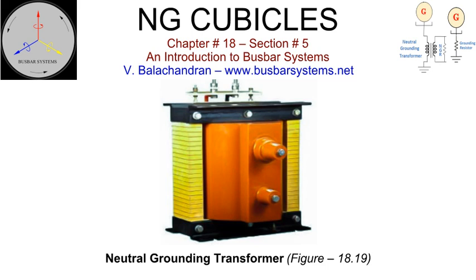Both the primary terminals of the transformer coil shall be fully insulated. They must be connected through a flexible connector of adequate size. This is to ensure that there is no stress on the terminals of the neutral grounding transformer during assembly, transport, or installation.